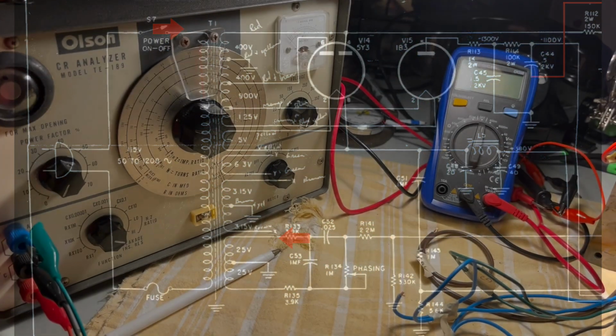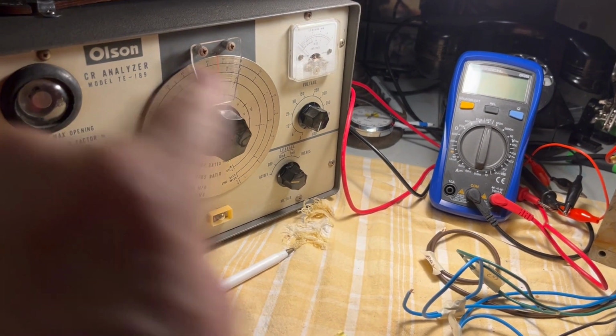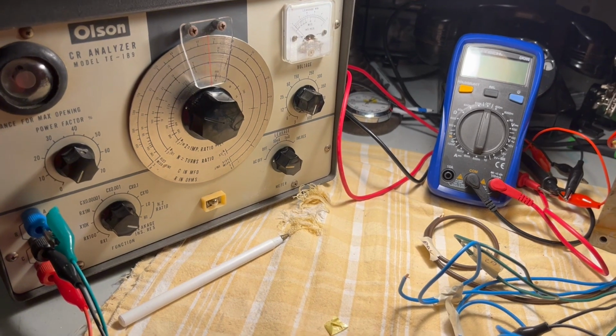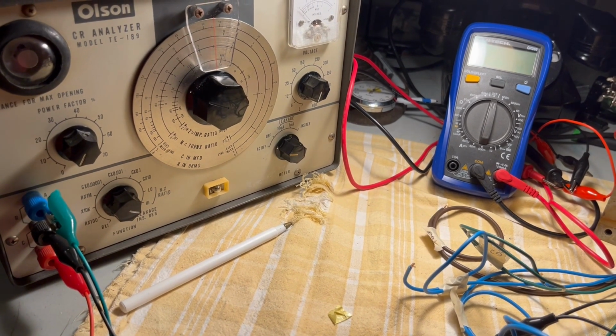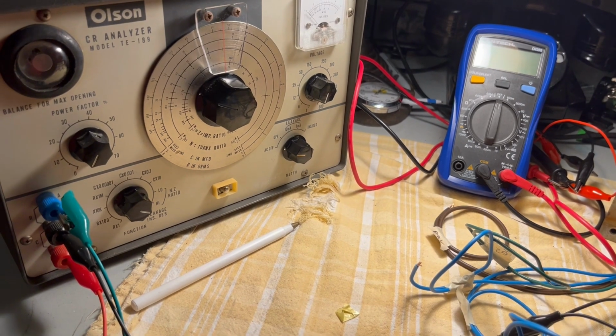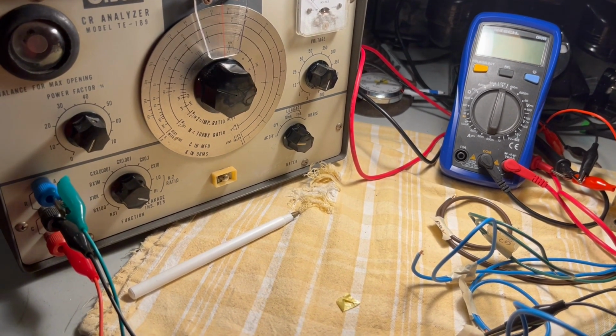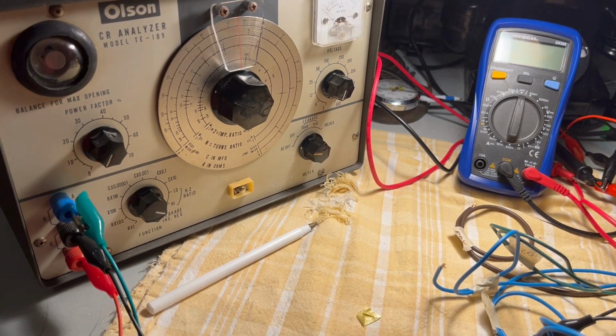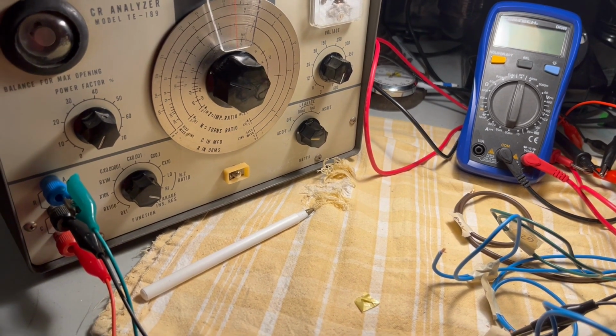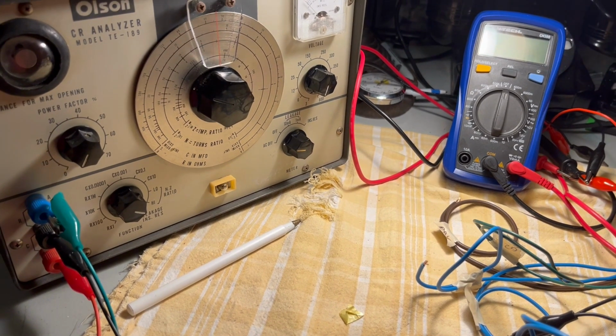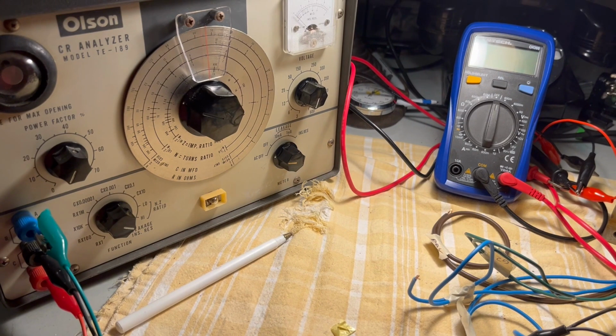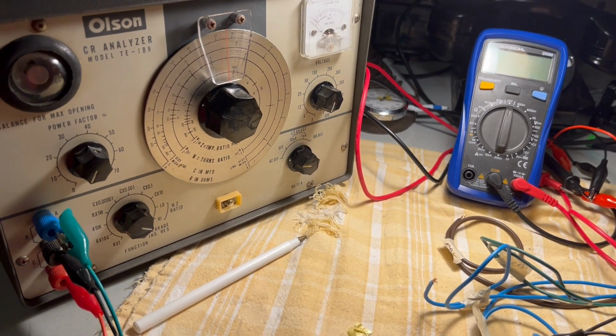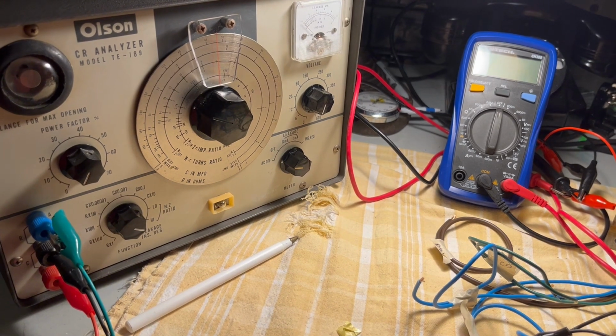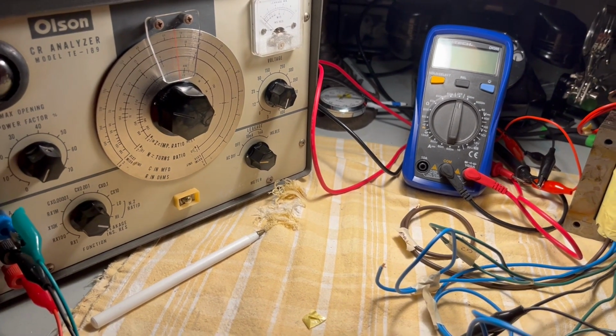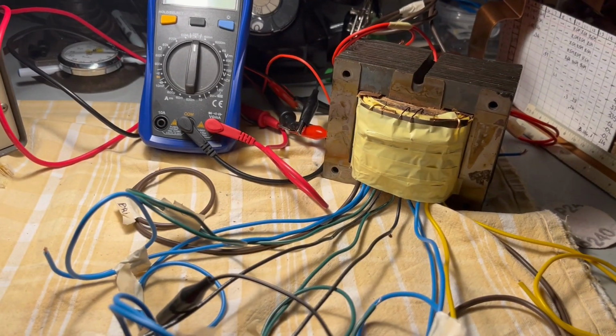So when I measure it, when I even use this thing, it only works when they're going in the same direction, which means that the coil is rotating in the same way. If I'm attached to the primary, I'm comparing it against one of the secondaries in order to arrive at a turn ratio, what they call a turn ratio. And you can use that math to calculate the voltage that you would expect to see, or you can use it to say, if you knew the number of turns in the primary, then you would be able to calculate the number of turns in each one of the secondary coils. And that's essentially what we did when we rebuilt this thing.